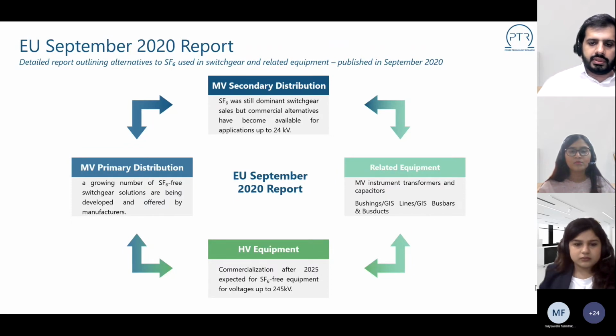The Commission was of the view that for medium voltage instrument transformers and capacitors, the potential alternatives at that time did not deliver satisfactory results, and they felt that instead of developing new products, following the best practices outlined in the regulations was a good idea. However, for medium voltage bushings, gas insulated lines, and gas insulated bus bars and bus ducts, penetration of alternatives could become relatively high by 2025 for certain voltage ranges.